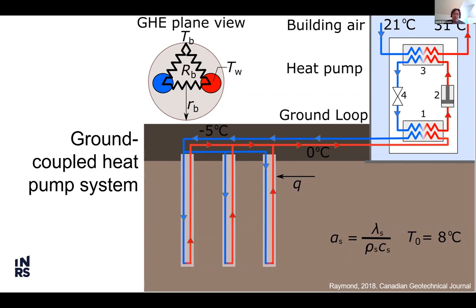Although we use renewable geothermal energy to operate the system and take that energy from the ground, these geothermal heat pumps are more seen as an energy efficiency technology because they consume some electricity to work. But by doing this, we can save about 60 to 70% of the energy we need to heat a building, and about 30–40% of the energy for cooling. And I guess the cooling application is probably what is most interesting for you in Colombia.